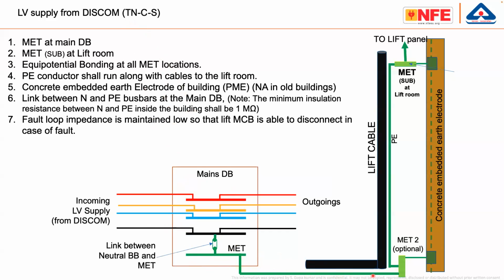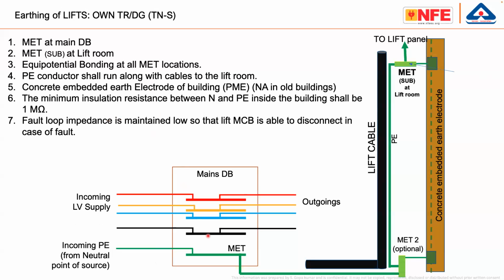Then there is an earth bus bar running along with the cable to the lift room. At the lift room, we have to make a common bus bar, let us say a sub main earth terminal, and the lift has to be connected to this particular MET. So basically, we are creating a smooth fault return path for the fault current to reach back to the neutral of the source. As a result, MCBs will be efficient in disconnection. And this is what, legally, we are supposed to do in a low voltage consumer premise. If it is a high voltage consumer premise, of course, it's a TNS system. Anyway, we will discuss it later.